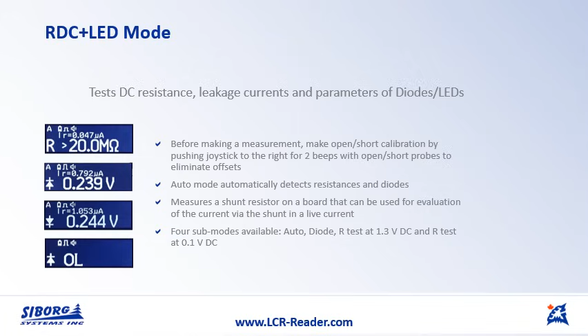RDC plus LED mode. This mode is for testing DC resistance, leakage currents, and parameters for LEDs and diodes. The important feature of this particular mode is the ability to set up a shunt resistor on a board that can be used later for evaluation of the current flowing across this particular shunt resistor. It's just a recalculation of the voltage apparently, but it's very useful. You don't need to recalculate on a piece of paper, you just get it done on the screen of your device.